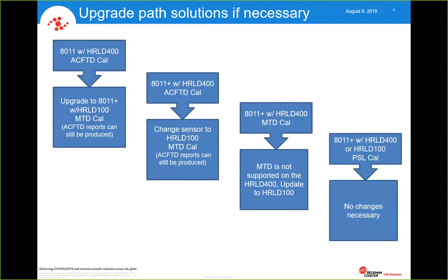If you have an 8011 Plus with a 400 sensor or a 100 sensor with a PSL cal, in the last scenario, you don't need any changes. So it really affects any customer that has an HRLD 400 sensor with an AC fine test dust cal. Then we can upgrade you to the 100, perform the new calibration, and then you're basically good to report out any reporting standard that you wish to do so.